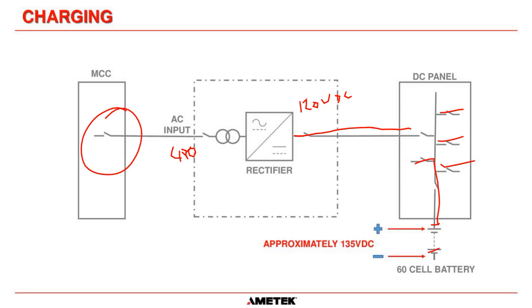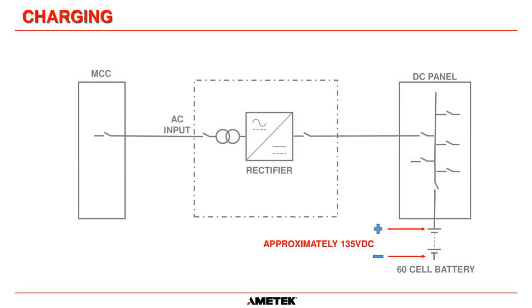Now, remember I said it's a nominal 120 volts, but we have to charge it at the battery manufacturer's recommended amount, which is 2.25 volts per cell. So the voltage is going to be approximately 135 volts DC. And there's a reason why I say approximately.